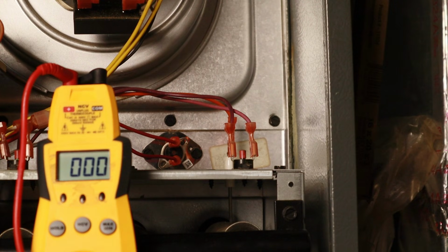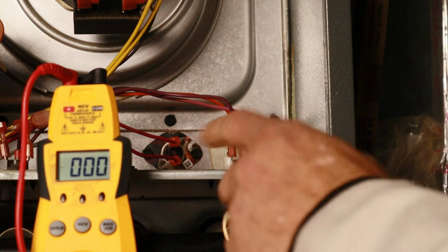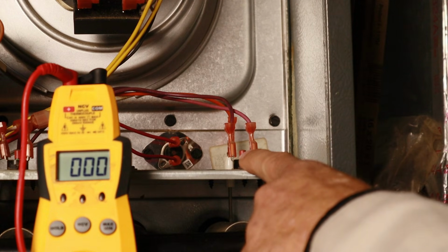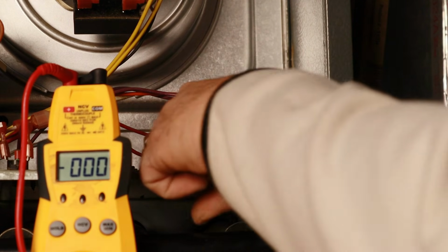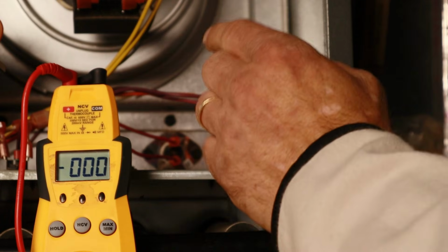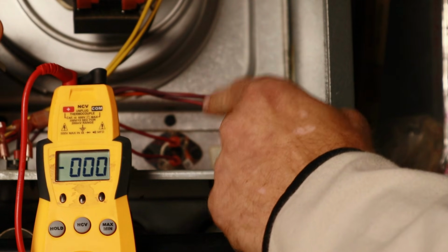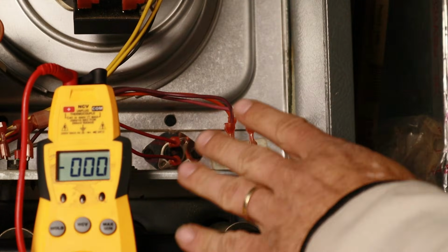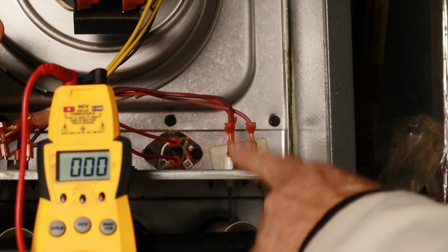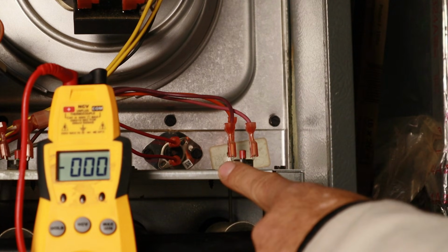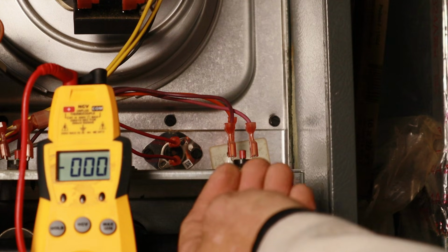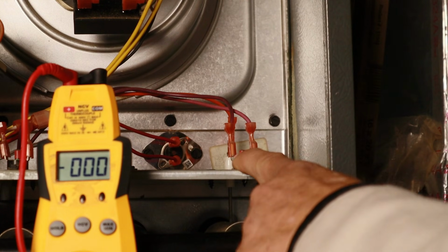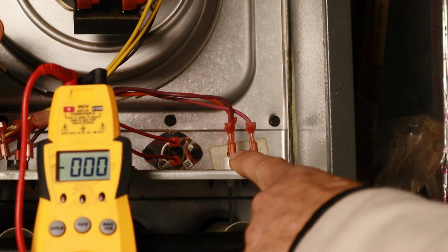Most furnaces that I've worked on, those safeties are going to be either one of two, sometimes both. It's going to be either a flame rollout switch or a thermal high limit switch, which is a probe that goes into the heat exchanger to monitor the temperatures inside. So both of these are temperature switches. The flame rollout is basically what it sounds like. If the flame starts rolling out of the furnace, it will open this switch, kill the 24 volts that's coming from the fuse going to the R terminal on our terminal block on our control board.